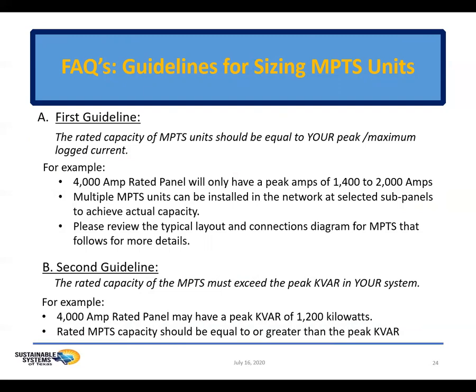Brian? Okay, the first guideline is we never size the unit or the units by the size or the rated amps of the panel. We size by finding the kVAR and harmonics of the system. The MPTS units each have a rated kVAR. An H240 can recycle 200 kVAR. An H490 can recycle 400 kVAR. And an H720 can recycle 600 kVAR.